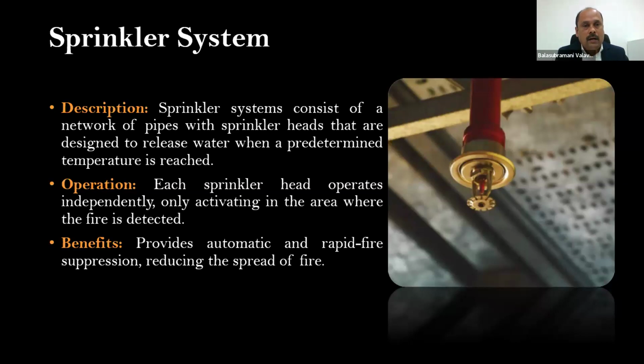The benefit is that it provides automatic and rapid fire suppression, reducing the spread of fire. When it comes to the kinds of bulb, orange is 57 degrees, red is 68, yellow is 79 degrees, green is 93. In general, green will be used for all the deluge systems, especially for transformer protection. And blue, purple, and black are bulbs which can take up to 227. In case of some furnace-related activity, these black kinds of sprinklers will be used, because a furnace will always have a higher temperature.